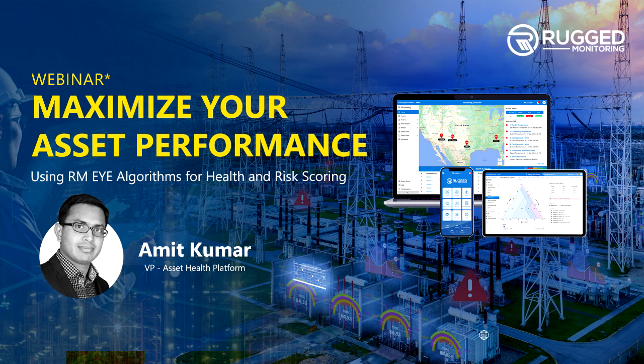With our APM system implementation, all of that has been automated. Service engineers have the APM software application on their tablets. They go for the visual inspection, filling the visual inspection report online on the tab using this APM application, and instantaneously the asset health index or health score gets updated. If any unusual activity happens, like a leakage, the asset health score will drastically go up, and an alarm and notification goes to the experts.